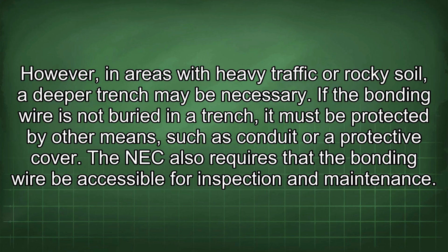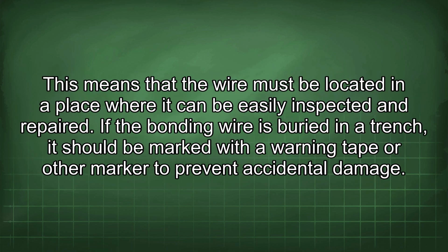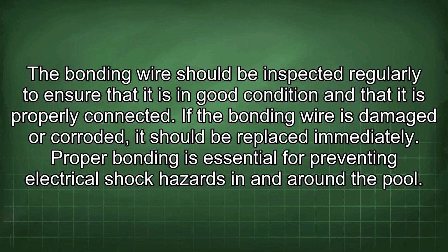If the bonding wire is not buried in a trench, it must be protected by other means, such as conduit or a protective cover. The NEC also requires that the bonding wire be accessible for inspection and maintenance, meaning it must be located where it can be easily inspected and repaired. If buried in a trench, it should be marked with warning tape or another marker to prevent accidental damage, and inspected regularly to ensure it is in good condition and properly connected.